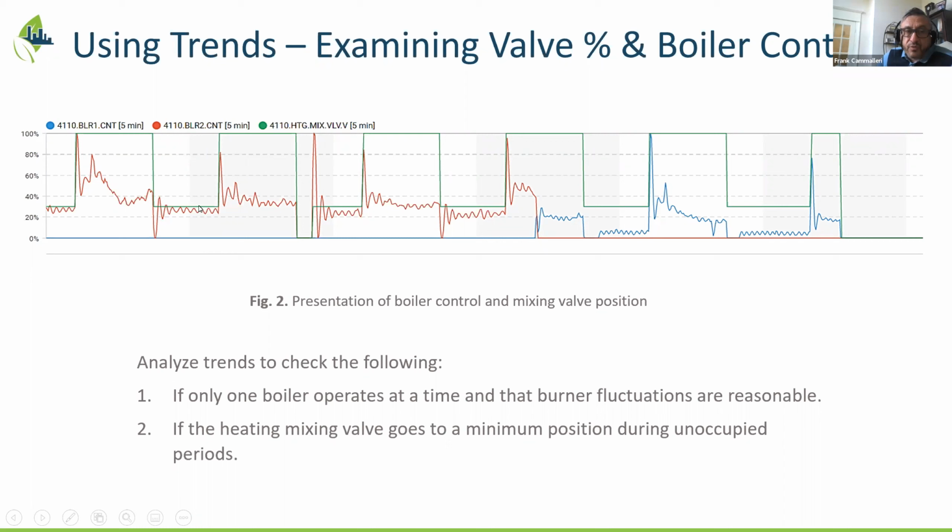So one of the solutions was to, okay, let's just put a minimum position. Well, they just arbitrarily chose 30%. Okay, and so again, the measure was working reasonably well, and then someone took some action to try to deal with an issue, and this is what happened.